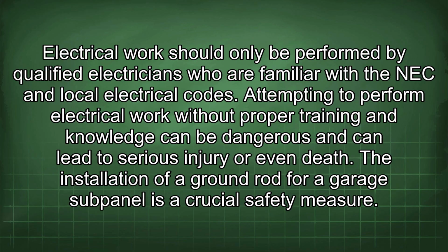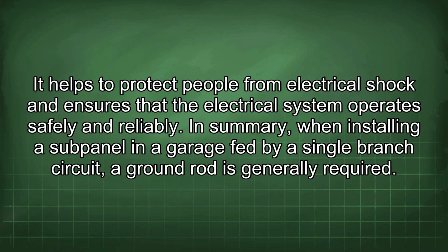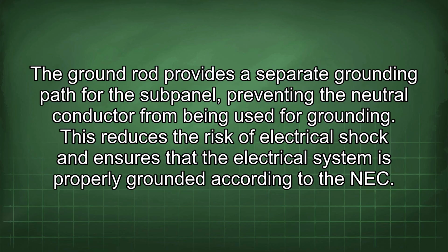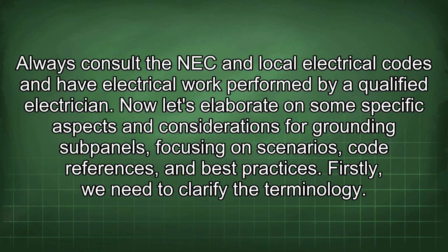even death. The installation of a ground rod for a garage subpanel is a crucial safety measure. It helps to protect people from electrical shock and ensures that the electrical system operates safely and reliably. In summary, when installing a subpanel in a garage fed by a single branch circuit, a ground rod is generally required. The ground rod provides a separate grounding path for the subpanel, preventing the neutral conductor from being used for grounding. This reduces the risk of electrical shock and ensures that the electrical system is properly grounded according to the NEC. Always consult the NEC and local electrical codes and have electrical work performed by a qualified electrician.